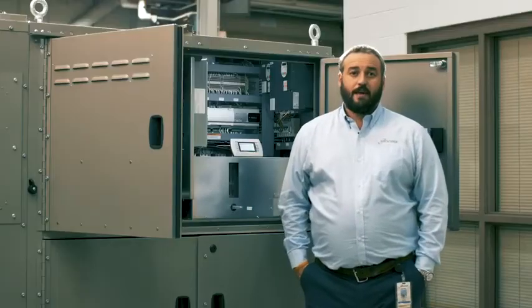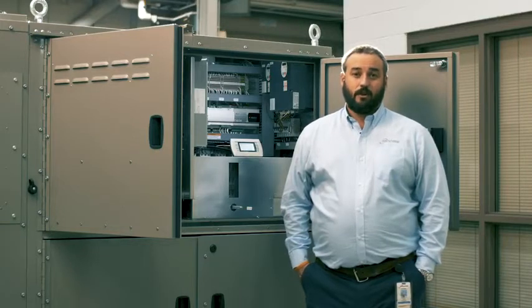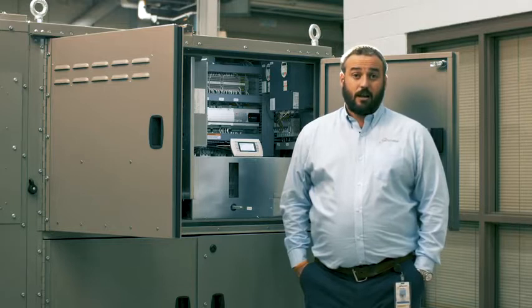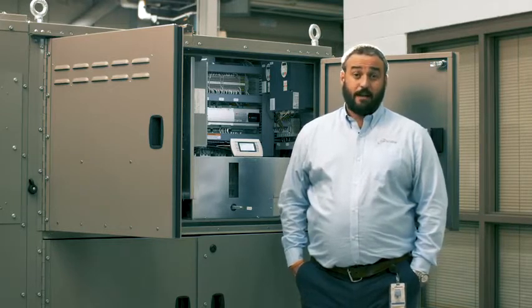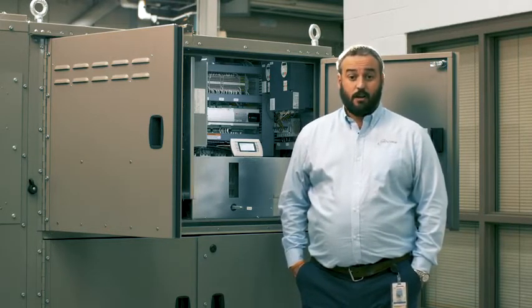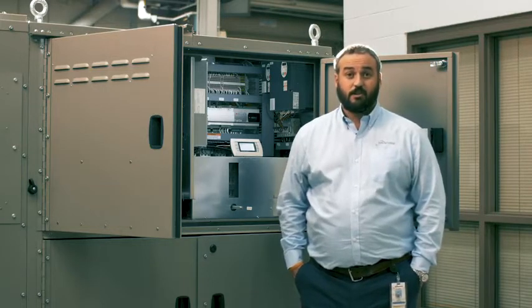We also offer 80 alarms, so the customer, without going up onto the roof to actually inspect the unit, can view via the BMS and see what alarm and what issues he has before he even has to go to site. So all of these 200 variables can be sent via the BACnet interface out to a building management system. So a customer could have it in his office, and it'd mean that he didn't have to go up to the roof to actually see how the unit was operating.